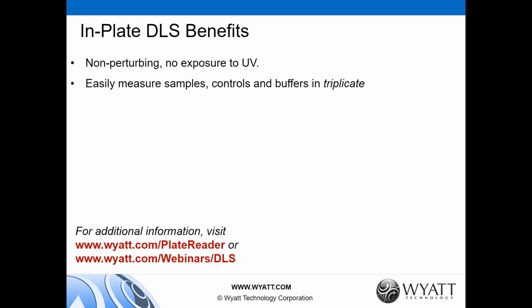Now, you may wonder why that's a concern, but of course, it's been established that there is a risk of ultraviolet light causing aggregation in proteins, and especially drastically for ADCs, antibody-drug conjugates. So some of the other techniques that you may be using to assess stability and aggregation might use ultraviolet light, and there is a concern about it causing aggregation, but that doesn't happen in the DynaPro.